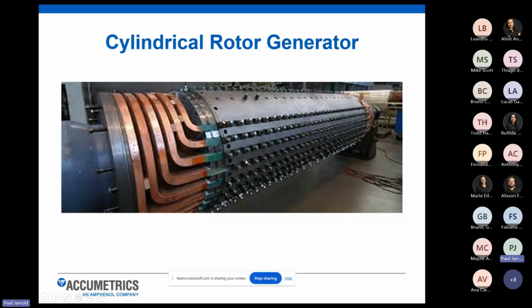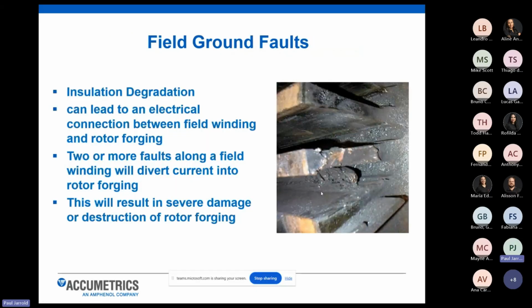And if you have two faults develop, that's the worst case scenario, where all your current is diverted into the generator rotor and can cause really significant damage to the machine. So here's another picture on the right to show you where that damage happened on a customer's machine, where the ground fault happened inside the slot and caused burning of the generator rotor. And the customer had to pull the unit offline and repair the damage.